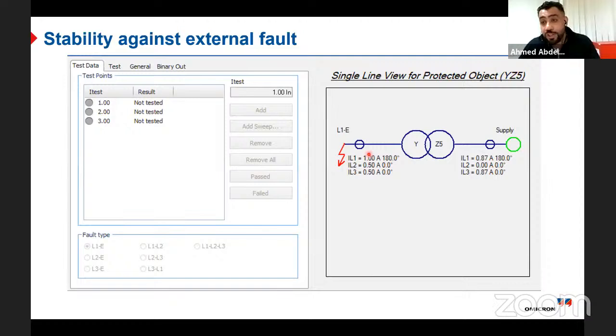Then you can switch. You can say, hey, I don't need a fault here on the high voltage star side. I need it on the delta side. Then you can go to the general tab, press in general, change the fault side and change the supply side. So you will see that the fault will become here and the supply will become here. It's a very, very important test to confirm that your system is stable against the external fault. This is the first requirement of any protection system, that it is secured against the external fault.